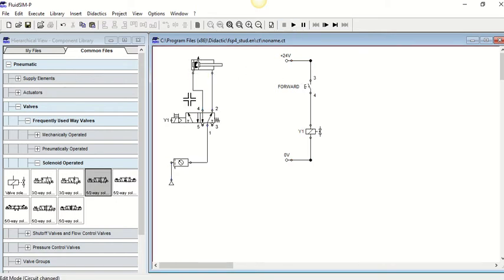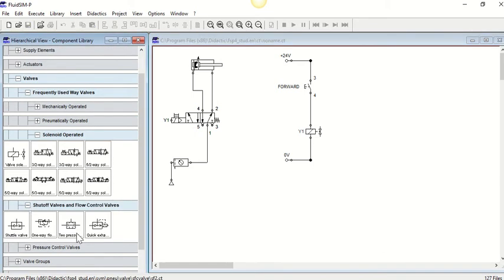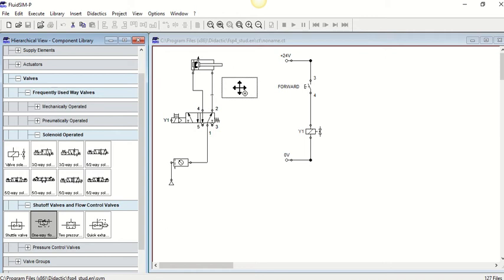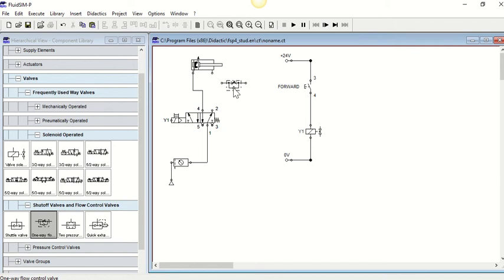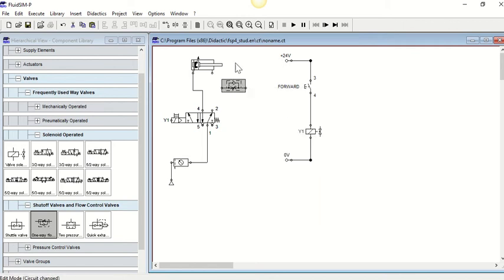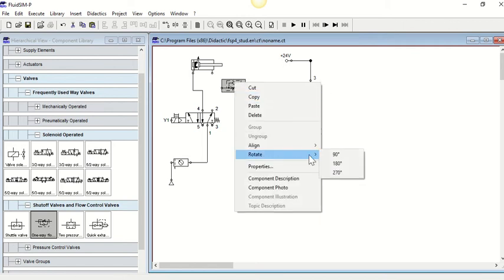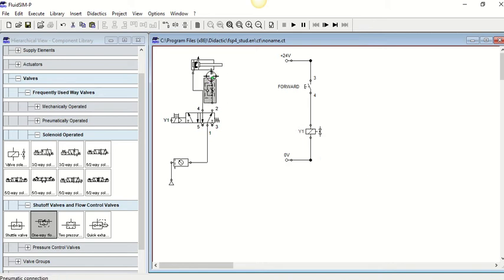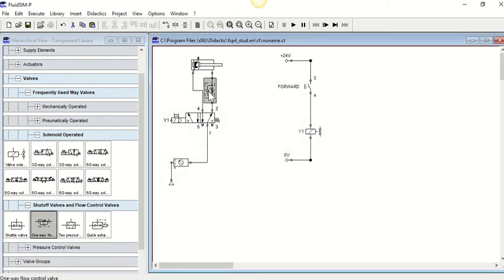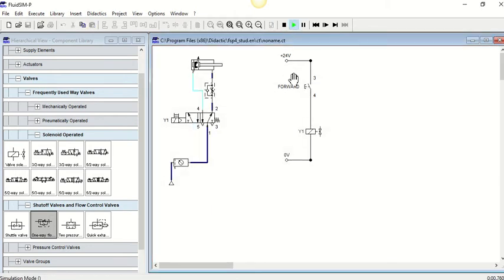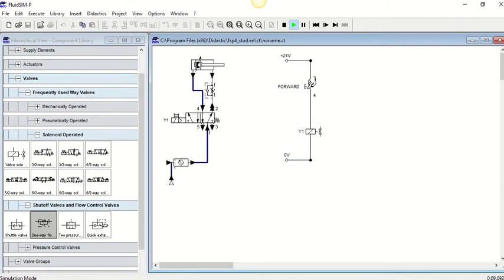Now what you'll also see is if I just slow it down a bit and put in a one-way flow restrictor, I want to slow it down on one side. We'll go meter out to slow down the speed but maintain the power. Let's really slow that down. You'll see I'm limiting its speed on the forward stroke but it's not going to fall away forward for me.